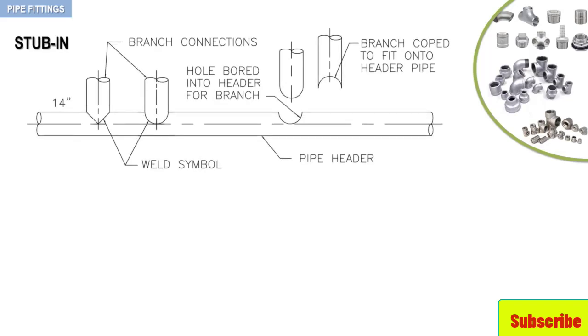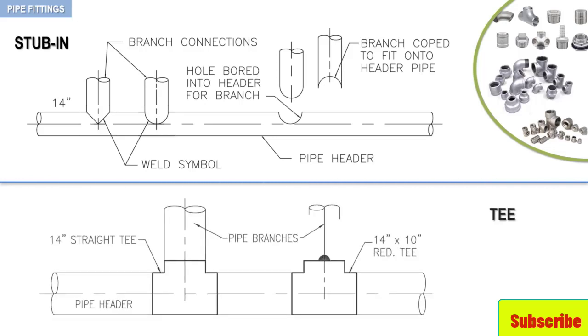Although the use of the stub-in is limited by the pressure, temperature, and fluid within a pipe, its use is becoming increasingly popular. Its chief advantage over the T is cost. Not only is a cost saving realized in the purchase of the fitting, but also in the installation. The stub-in requires only one weld while the T requires three. Although the cost of boring the hole and coping the branch must be factored in, the overall expense of fabricating a stub-in is much less than the purchase and installation of a reducing T.